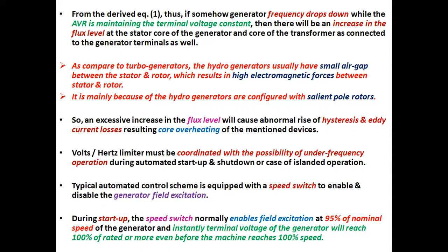So, an excessive increase in the flux level will cause abnormal rise of hysteresis and eddy current losses, resulting in core overheating of the mentioned devices. Volts-Hertz ratio limiter must be coordinated with the possibility of under-frequency operation during automated startup and shutdown or case of islanded operation.